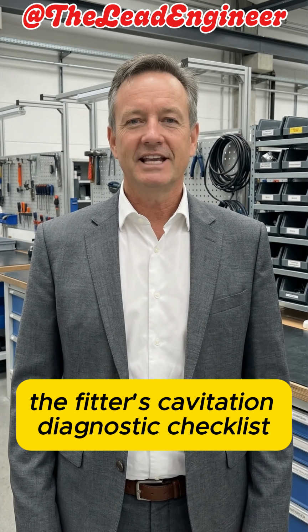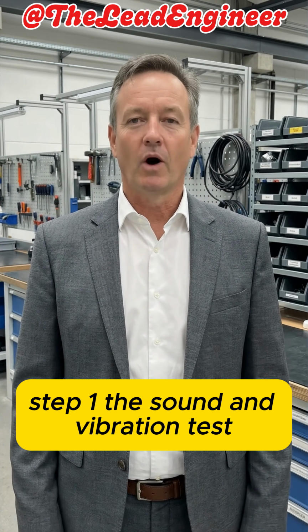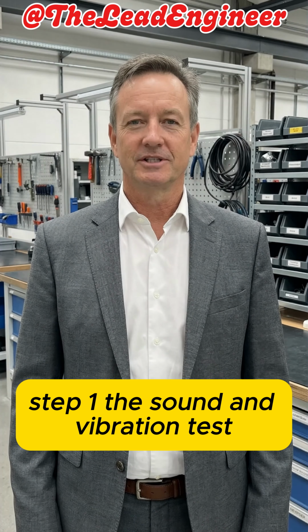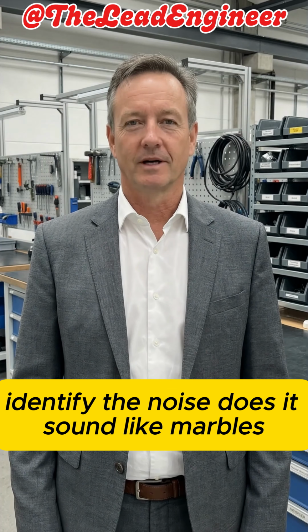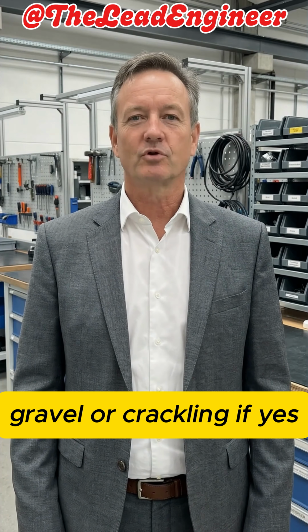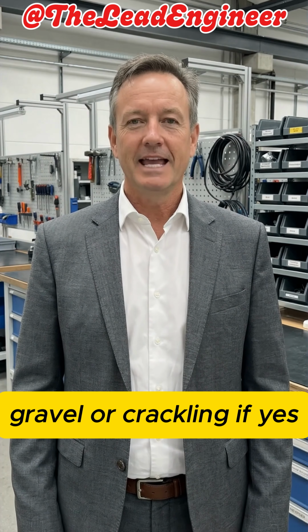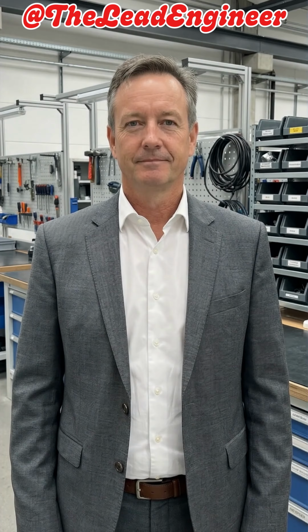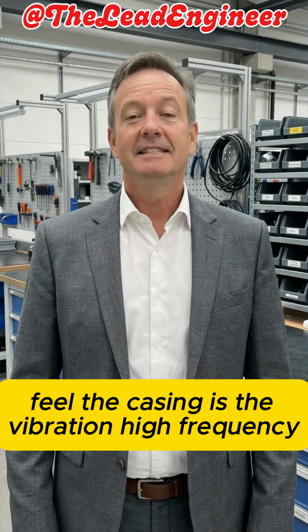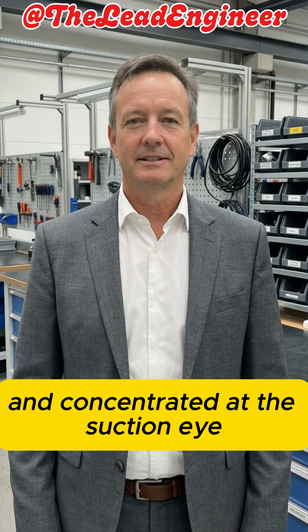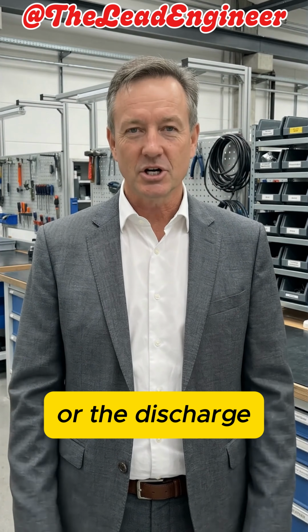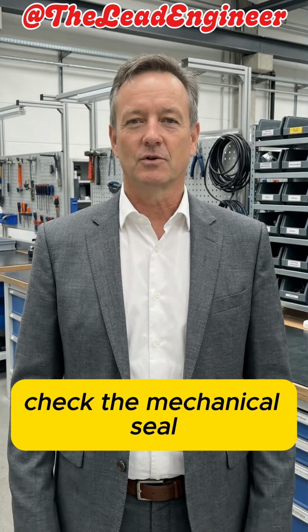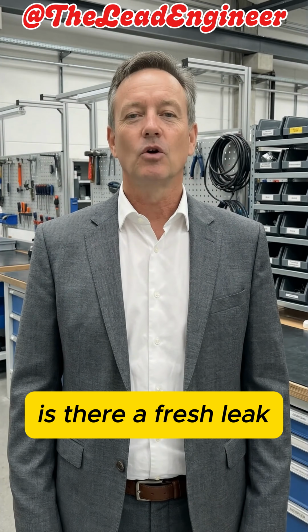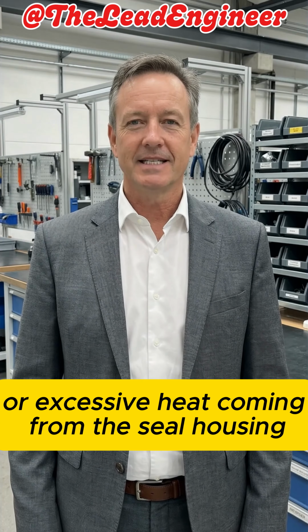The Fitter's Cavitation Diagnostic Checklist. Step 1. The sound and vibration test. Identify the noise. Does it sound like marbles, gravel, or crackling? If yes, it's likely cavitation. Feel the casing. Is the vibration high frequency and concentrated at the suction eye or the discharge? Check the mechanical seal. Is there a fresh leak or excessive heat coming from the seal housing?